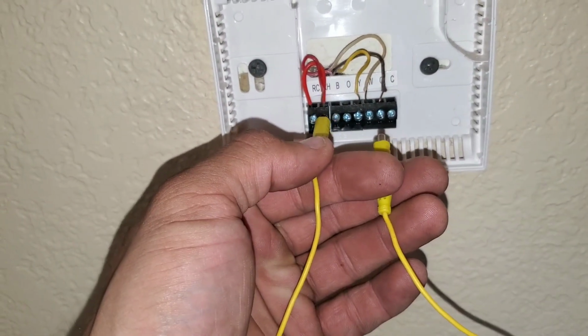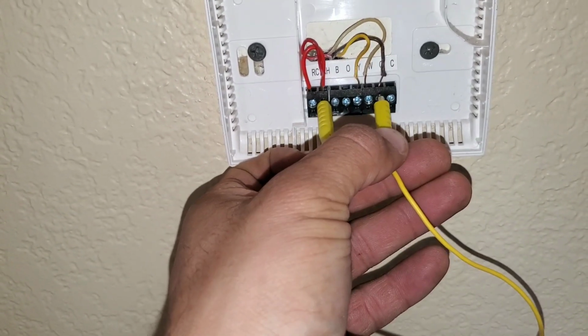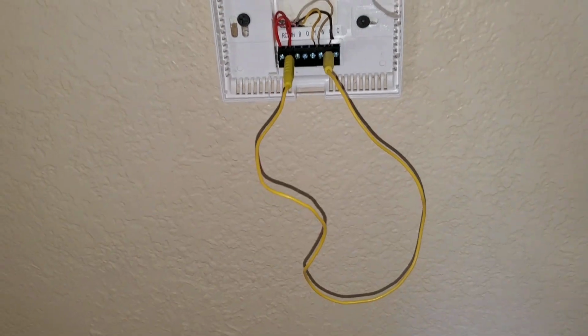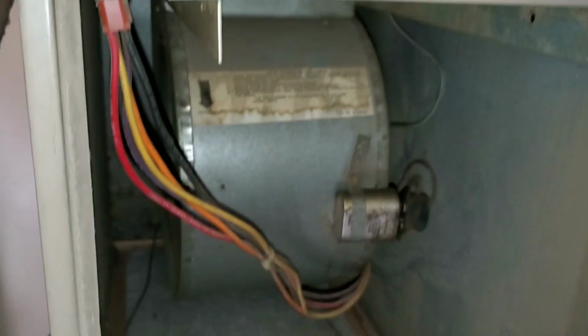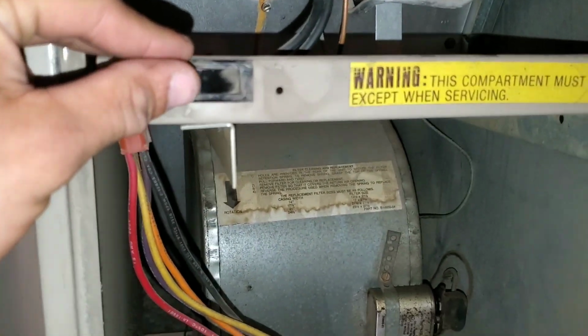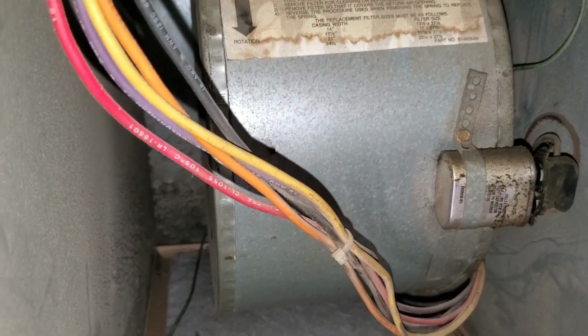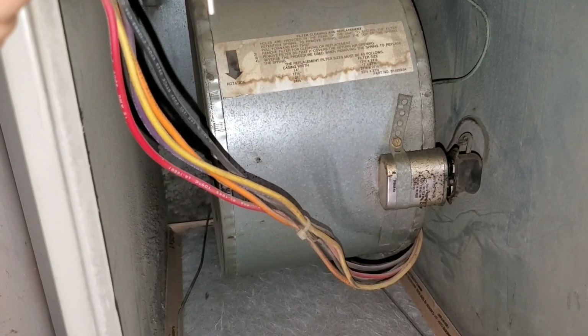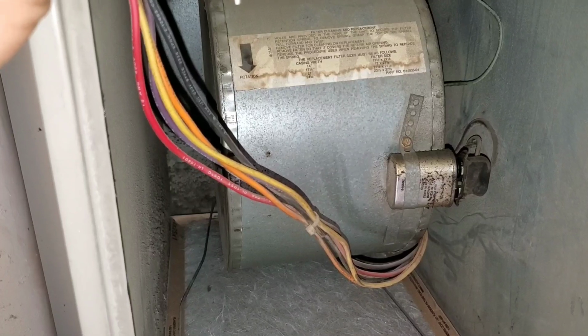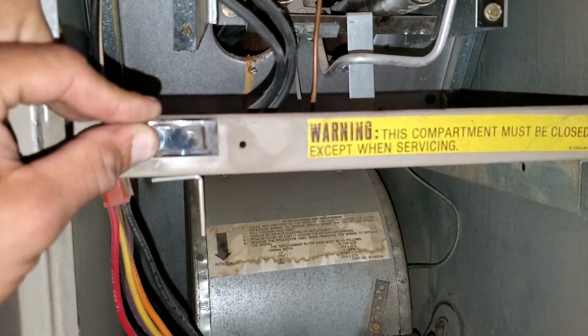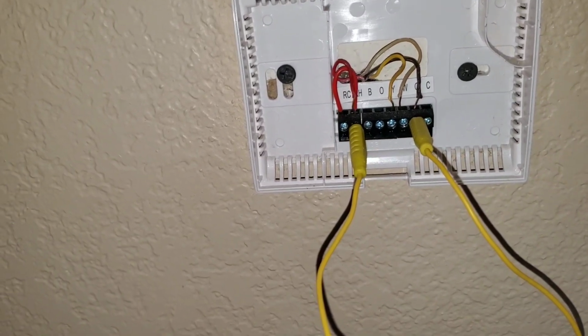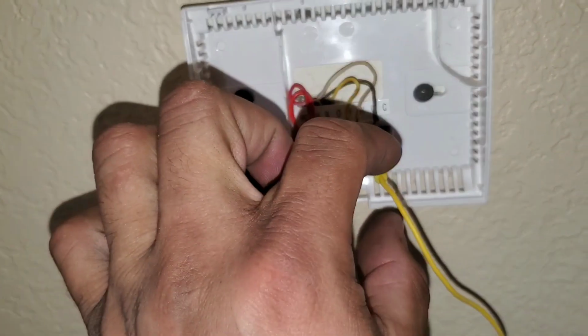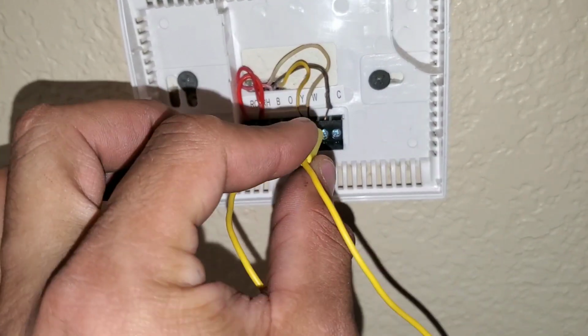I do have a jumper, so I'm going to jump my R to my G terminal, and my blower motor should turn on. So here I removed my panel. I am going to have to manually engage my door switch. So we do know at this point that we do have voltage coming from my thermostat when I jump my R and my G terminal. Now for this next test in troubleshooting, I'm going to quickly jump my R terminal to my Y terminal, and I'm going to see if my condenser unit turns on.